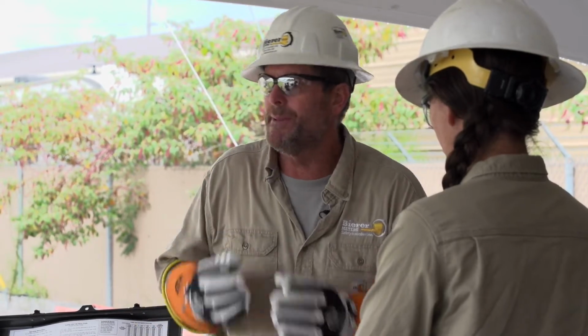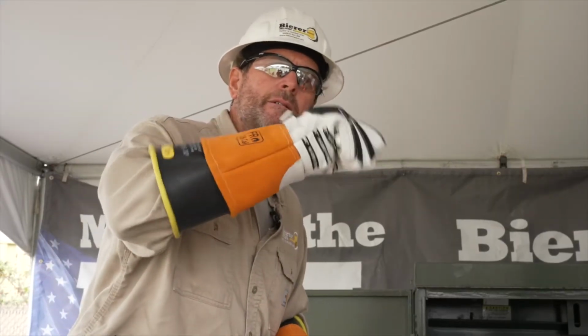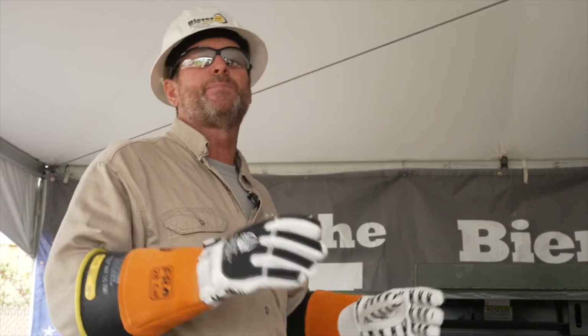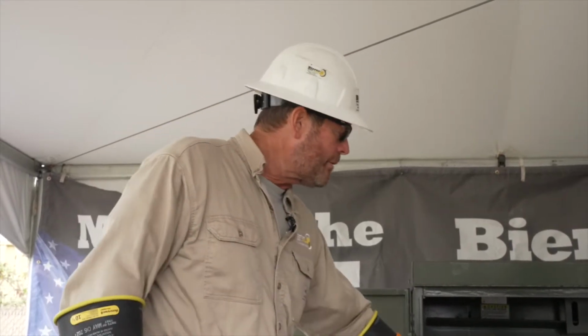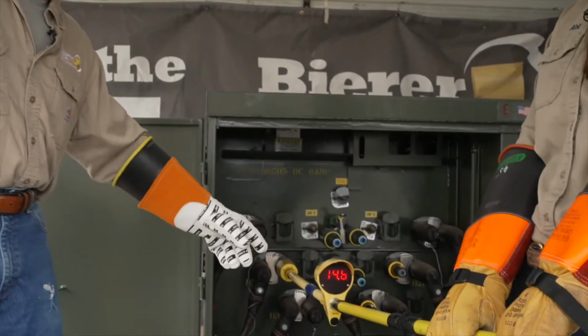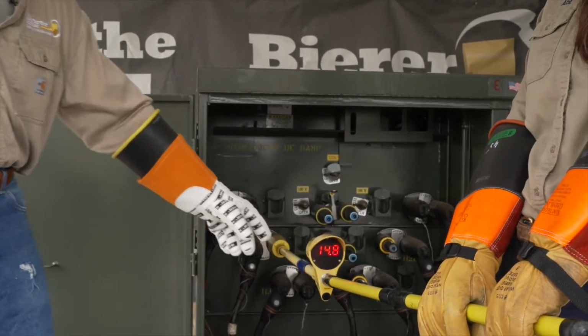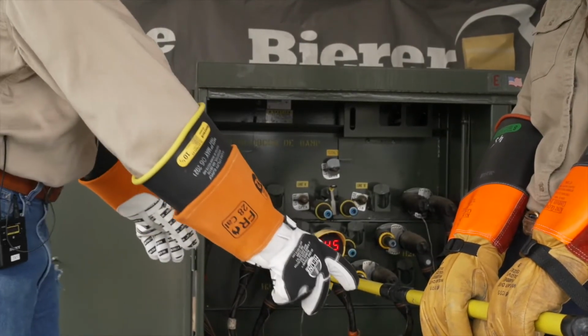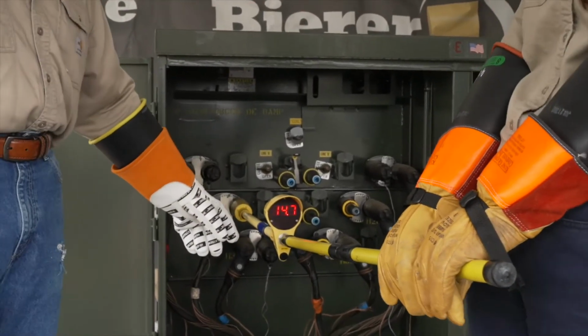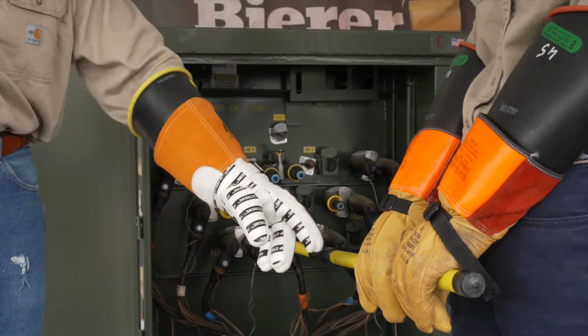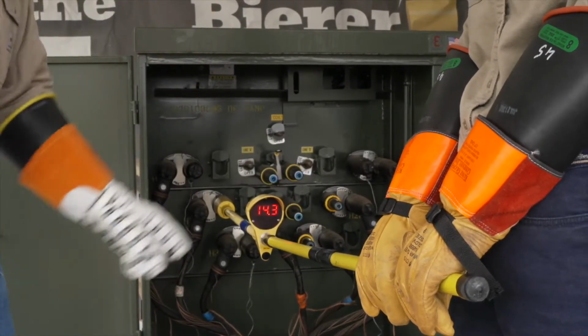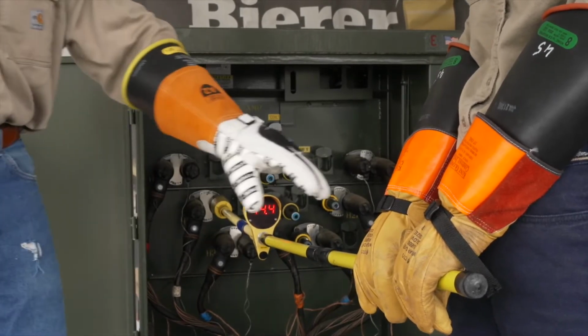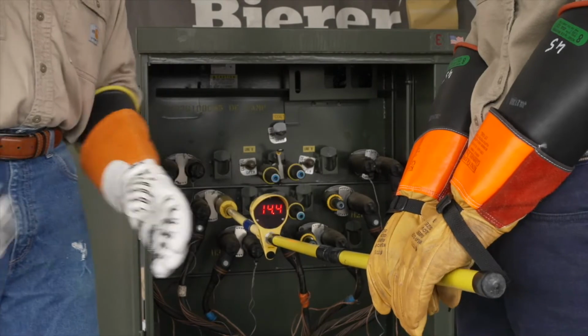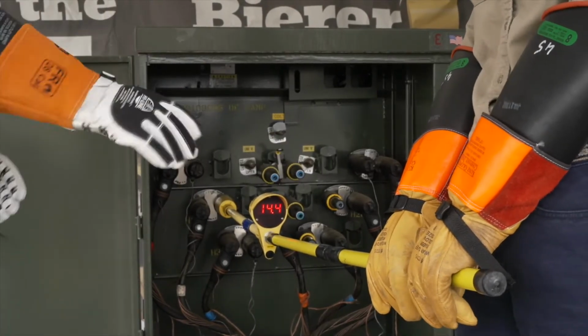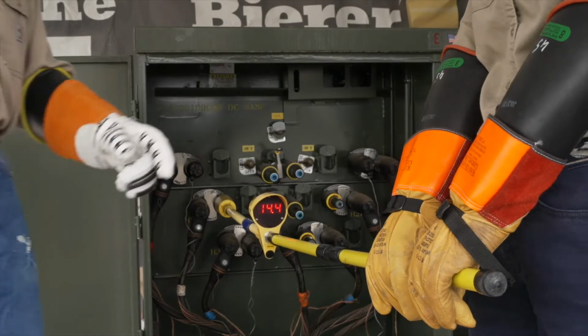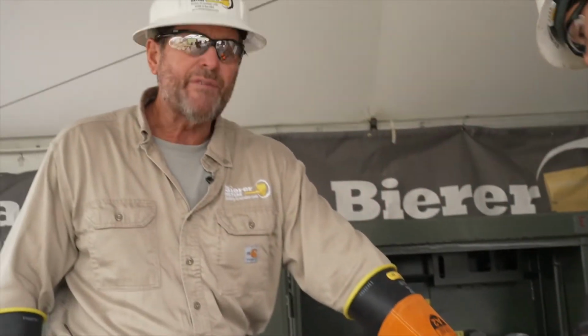It's not going to ask you for permission. It's not going to knock on the door. It just does it, in less than a split second. So when you're working the meter, stay away from that meter head. No short sticking, no tool gloving. Get back. We recommend 31 inches minimum from the device because of arc flash measurement, but I like to train 36, and that's widely accepted as 36 inches back on your hot stick.